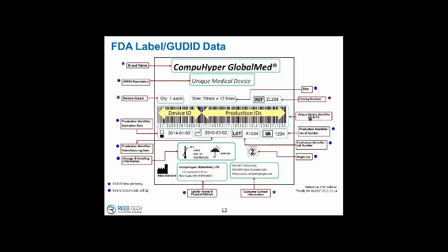So some are required, so the manufacturer needs to be identified. Obviously, this UDI in a human readable format and in an AIDC format needs to be there. Most companies elect to use a barcode or a 2D barcode, a single or a 2D barcode, and obviously description and so on. So I don't think we have time to evaluate each of these individual fields, but there are some guidances about what has to be on the label, and then as appropriate, there's some additional things that would be necessary. So hopefully that answers that question.